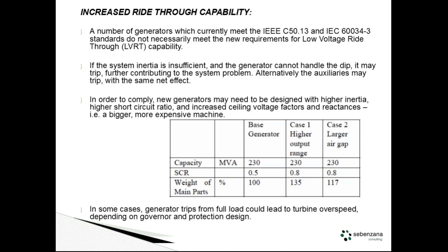Something else, possibly more a problem with smaller and older machines, is what happens when the generator trips from full load. If your protection is not properly set up, the turbine overspeeds — and we've seen that with non-Eskom customers. Every time you do that, the overspeed puts extra stress on the generator and turbine more than it's designed for. It can handle it a few times, but if you keep doing it, it's going to cause long-term problems.